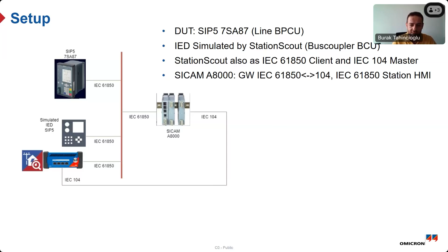Let's do this. We have load and see if it's really real, because if I now close this and want to connect to this IED, which is a physical IED, it would be available and reachable over this IP address. It looks like the commissioning engineer's work is in progress. Now they have this data model as we wanted. Even this GOOSE I can see, and I can also subscribe to it and see its value, and even sniff it if I just want to sniff GOOSE. So I also see the GOOSEs in the network. That's also a good indicator, and some reports also.